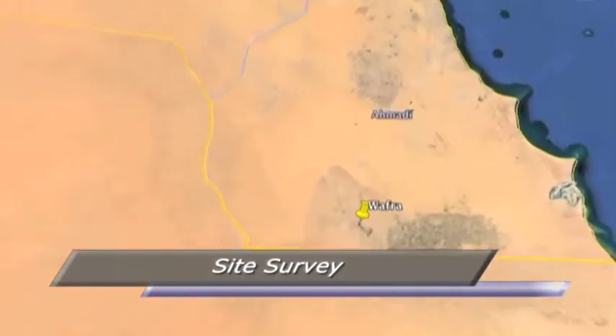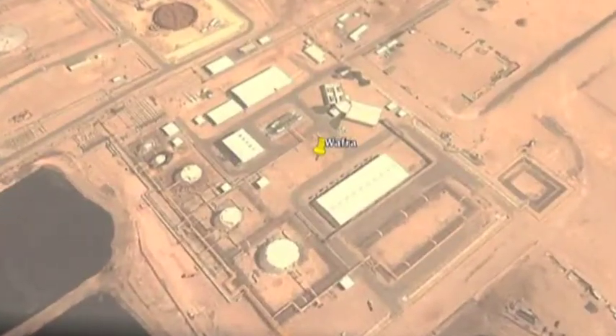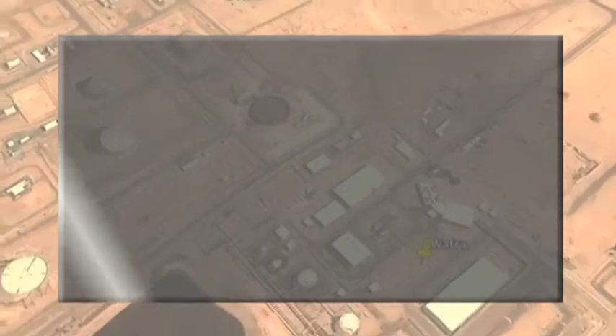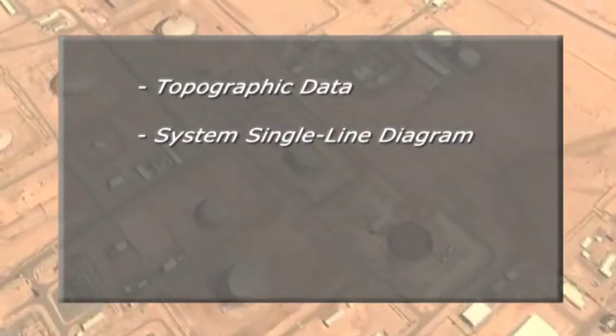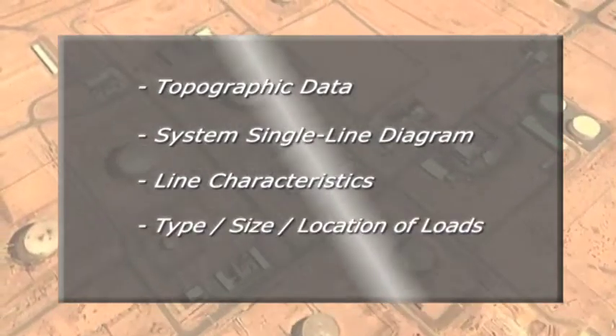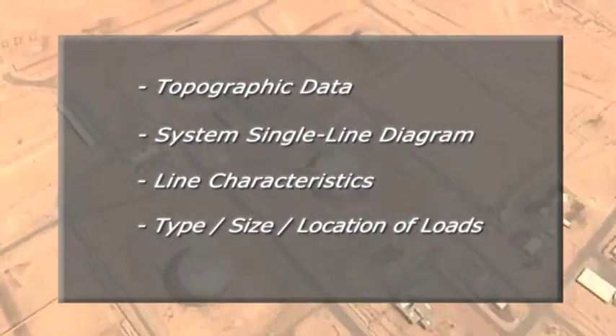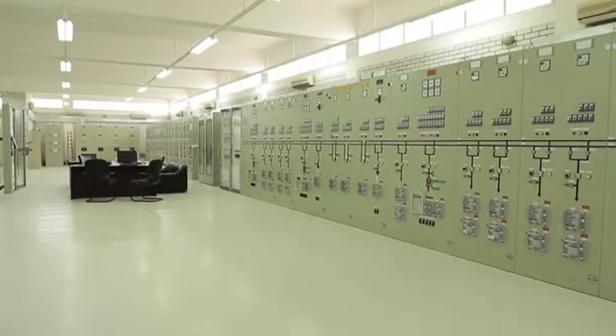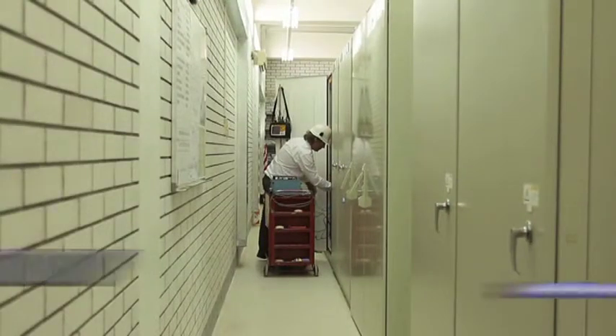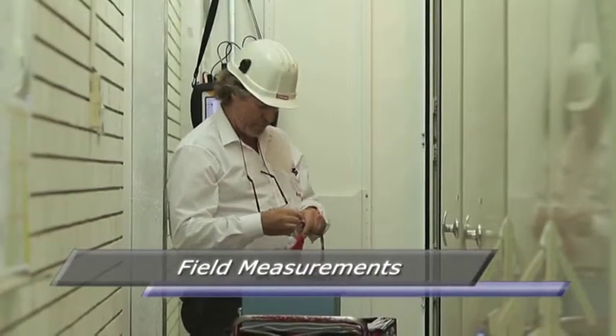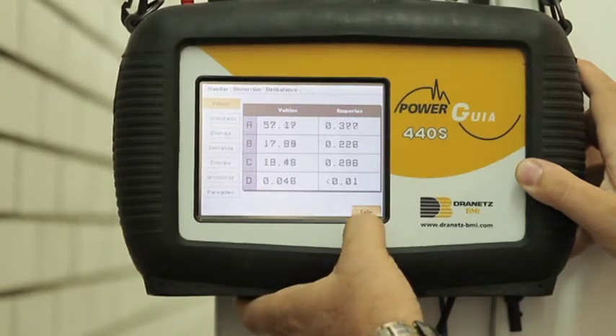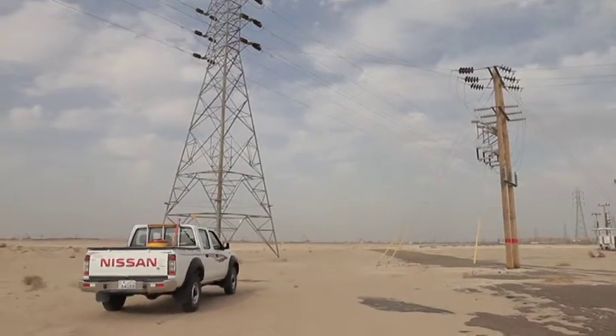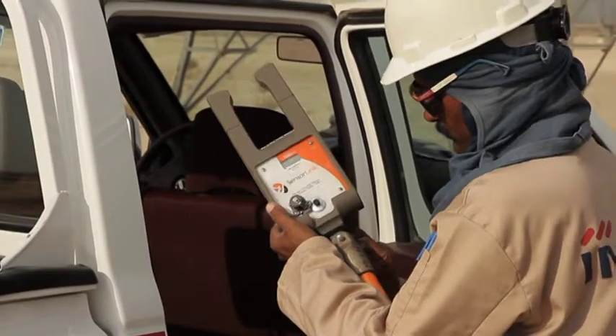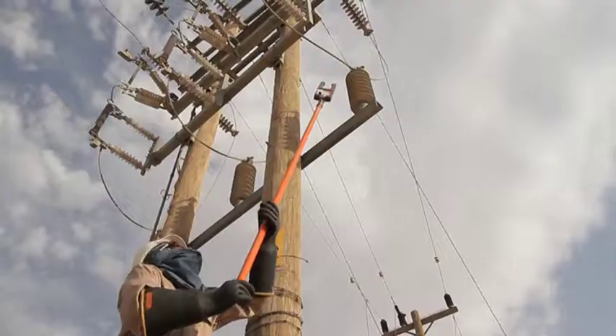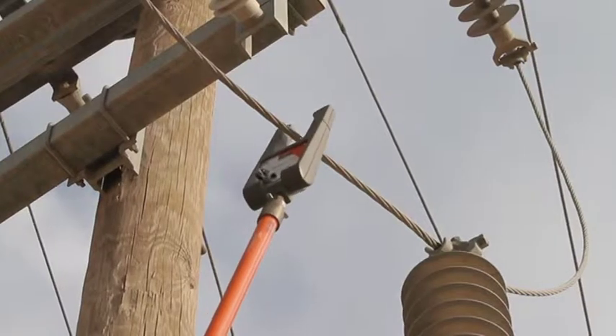First, a field survey was carried out, collecting all relevant data about the distribution system itself, such as the characteristics of overhead lines, the type, size, and location of loads, as well as additional topographic data, single-line diagrams, and so on. Then, a large number of voltage, current, and harmonic distortion measurements were taken at selected nodes of the distribution network. This was done using power analyzers wired to the secondary windings of existing instrument transformers, but also by direct measurements taken on the medium voltage feeders. Measurements covered periods of time long enough so to identify all possible load conditions of the feeders.